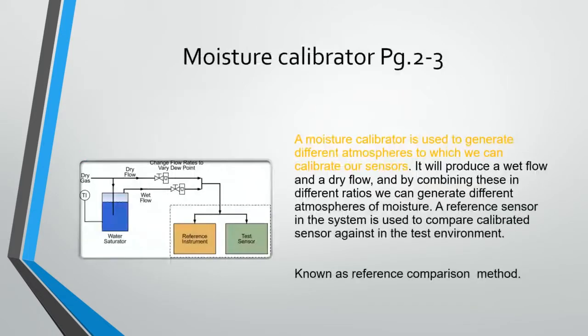The first standard we look at is called a moisture calibrator. It takes a dry gas, feeds it through a mechanism that saturates it with water, then blends that moisturized flow with some dry air to create a desired ratio of moisture. This simulated environment is fed into a chamber where both the reference instrument and the test sensor are compared — a reference comparison method. The definition: a moisture calibrator generates different atmospheres by combining a wet flow with a dry flow in different ratios.